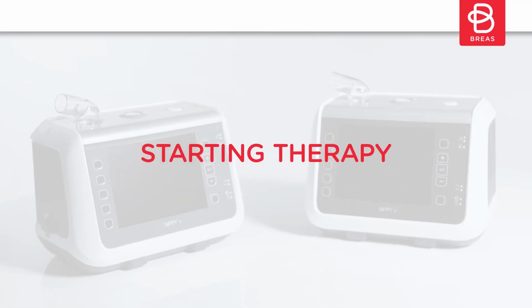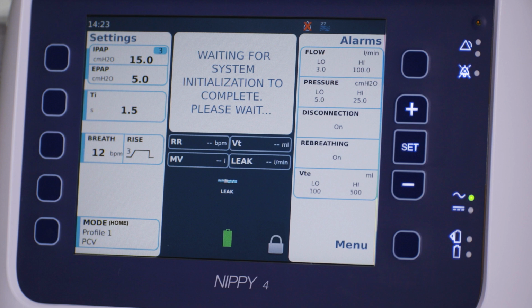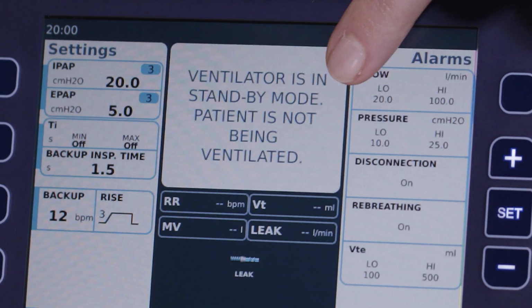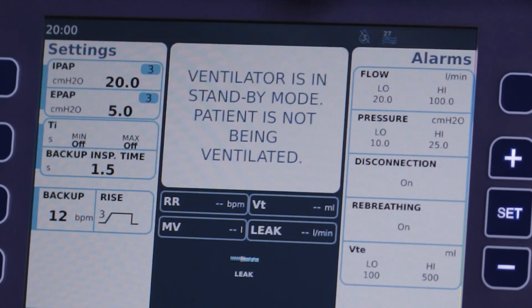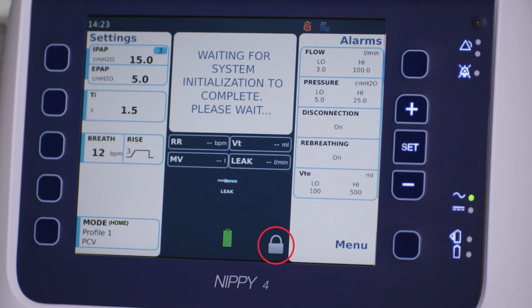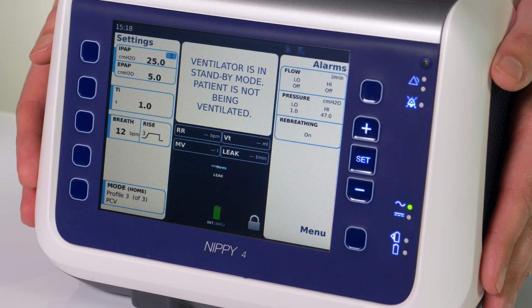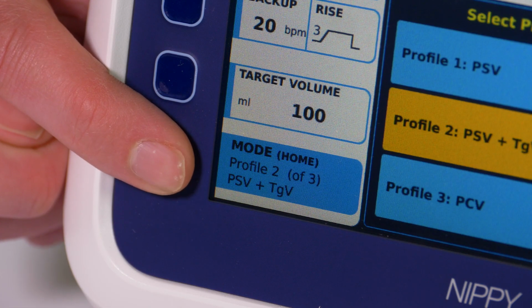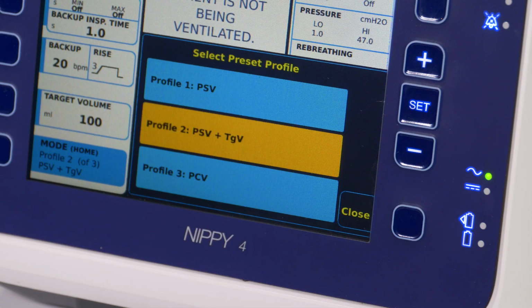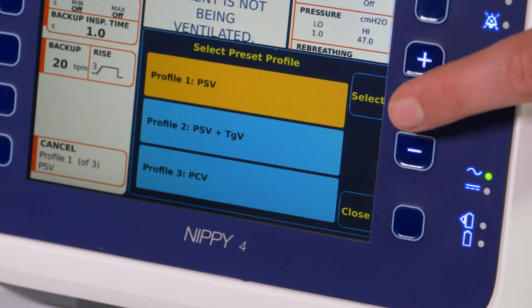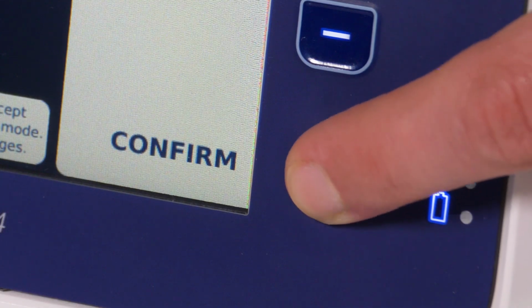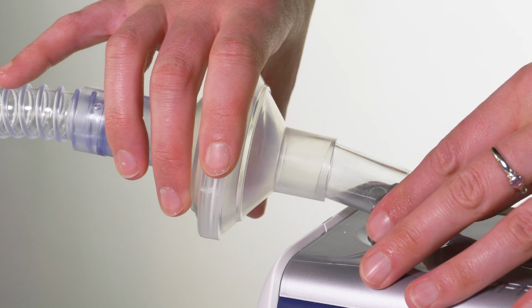Starting therapy. When the ventilator is ready to use, the screen will read, "Ventilator is in standby, patient is not being ventilated." Your ventilator will be locked into its home mode, so you will be unable to change any clinical settings. If you have multiple profiles set, please check via the mode box in bottom left-hand corner of the screen that the profile is correct prior to starting therapy, and that the appropriate circuit and interface is connected.